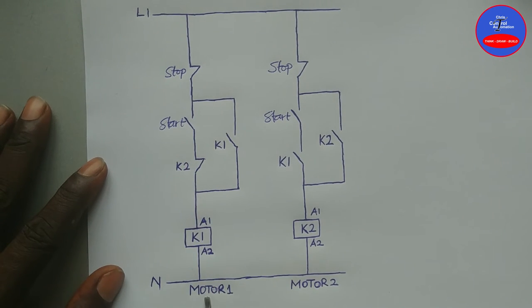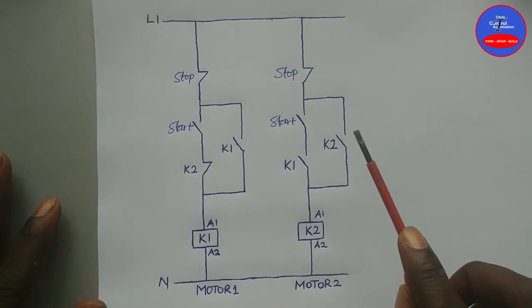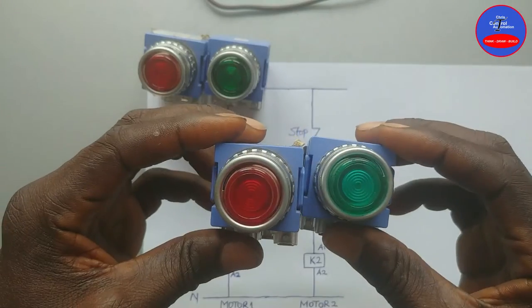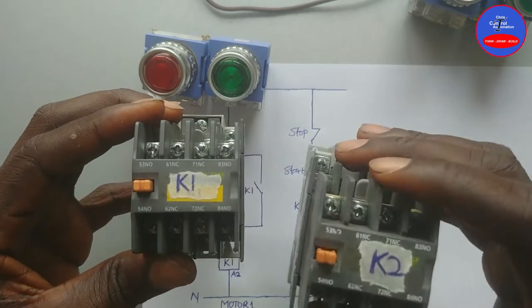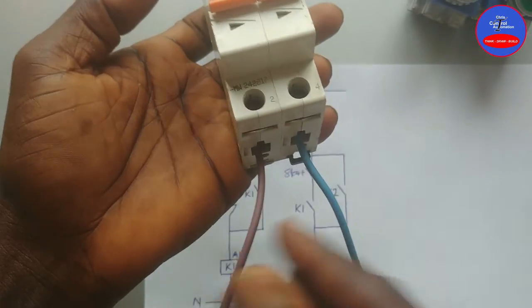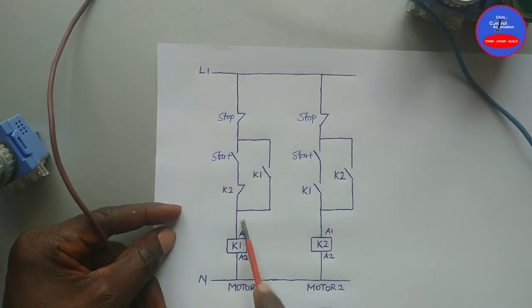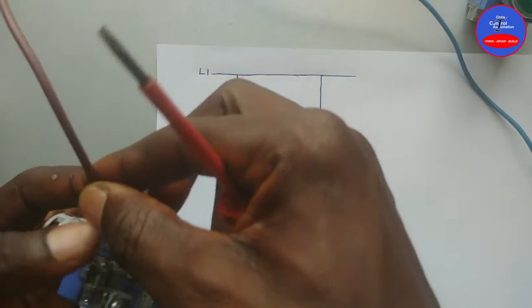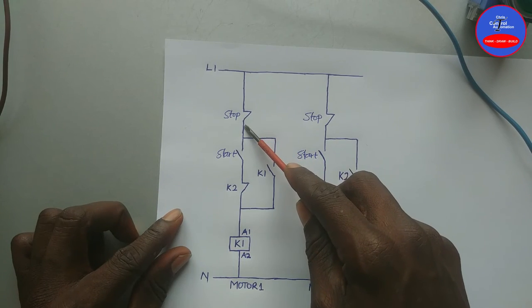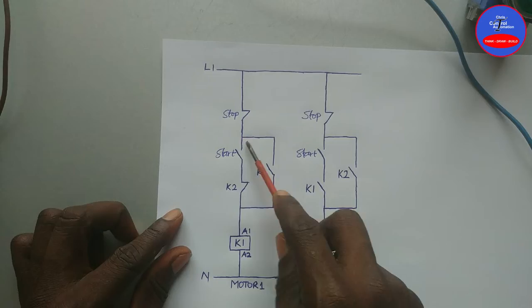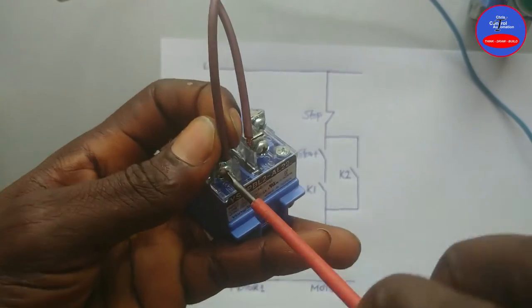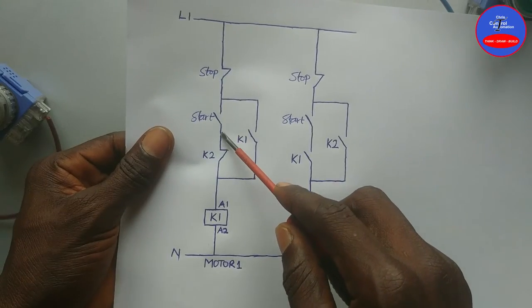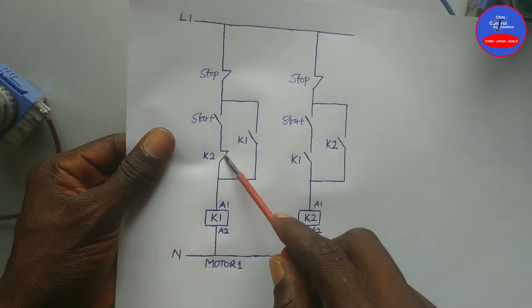This means that when Motor 1 and Motor 2 are both running and we stop Motor 1, there is no way we can restart Motor 1 unless we stop Motor 2. Let's see the wiring. These are Motor 1 stop and start buttons, Motor 2 stop and start buttons, K1, K2, our supply breaker, live and neutral. We are wiring Motor 1 from live; it comes to one side of the stop button, from the other side of the stop button it goes to one side of the start button.